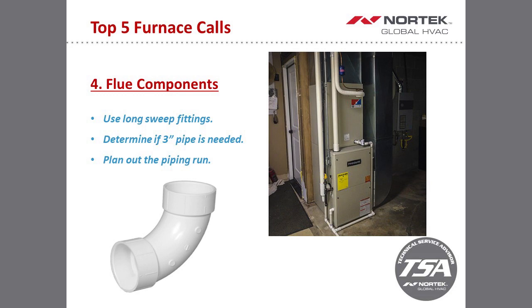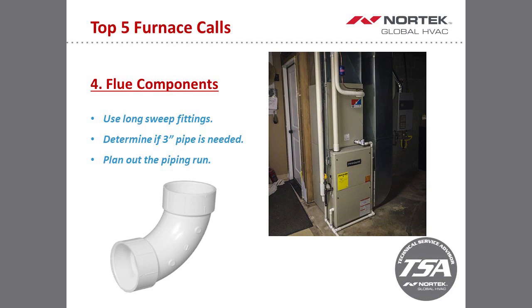When you go to 3-inch pipe on a furnace, let's say you have a 120,000 BTU 2-stage furnace and it requires 3-inch pipe. On all of our furnaces, the PVC coming out of the inducer is going to be 2-inch pipe. You then have to transition to 3-inch. So on a typical installation, what you'll have is the pipe coming out either the left or the right side on a 2-stage high efficiency furnace. The first fitting that you'll hit is the T, and then once you go vertical from the T, you'll want to hit 3-inch. So the only thing that we really tell guys from the tech department is go to 3-inch as quick as you can on that vertical run.